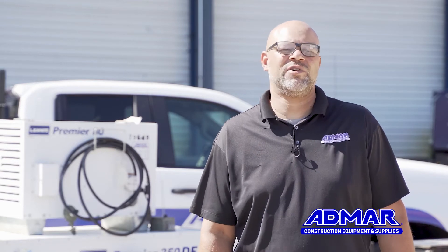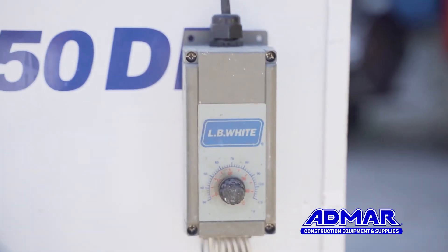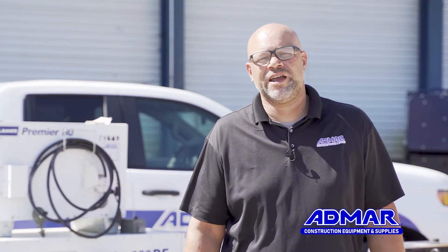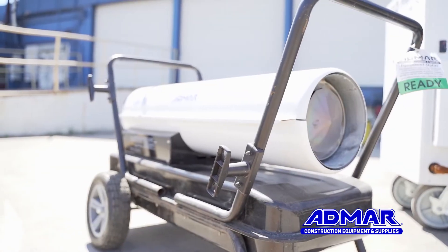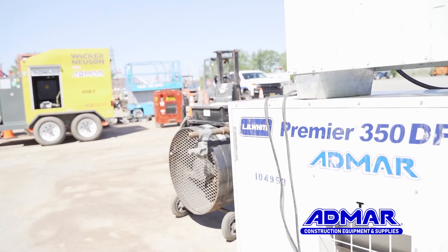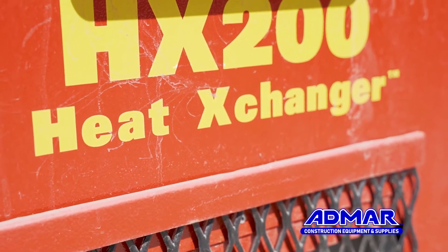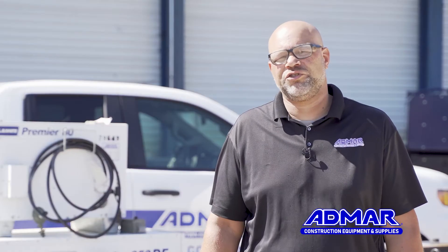The first type of heat we'd like to talk about is direct fired heat. Direct fired heat is an economical solution for heating a large space in your project. While these heater types are 100% efficient, there are some challenges when it comes to carbon monoxide and moisture within your project. The most common is the salamander style, which is an open flame heater that draws air over the flame to create a heat rise. Another type is the makeup air style, which encloses the flame within an exchanger, superheating air over that chamber, and then distributing it within the project. This helps with both moisture and carbon monoxide, as there are many air exchanges with these high CFM models.